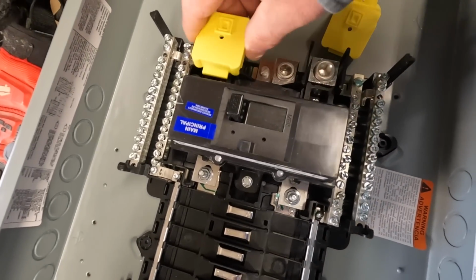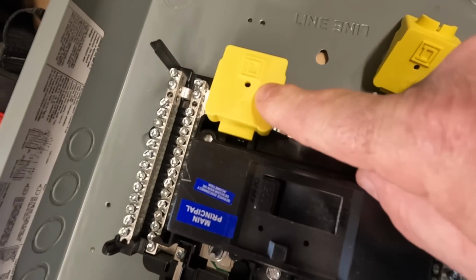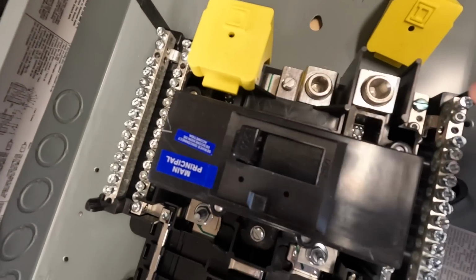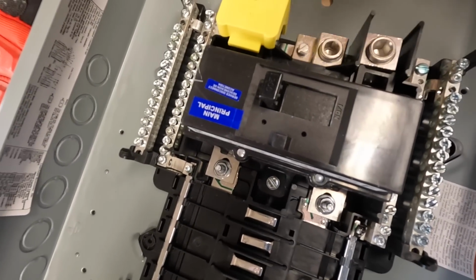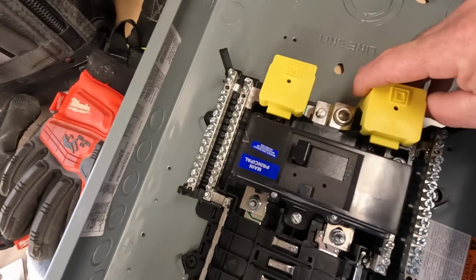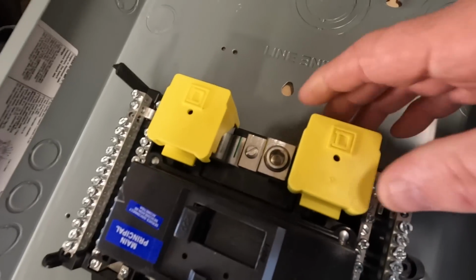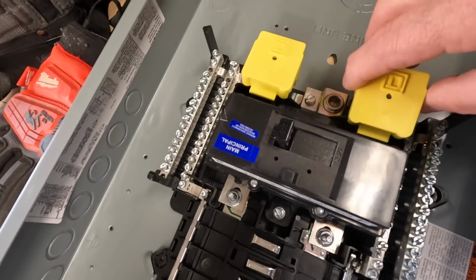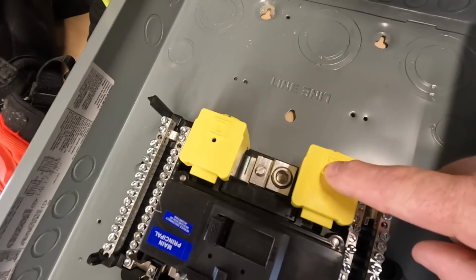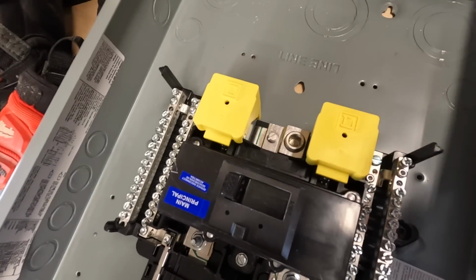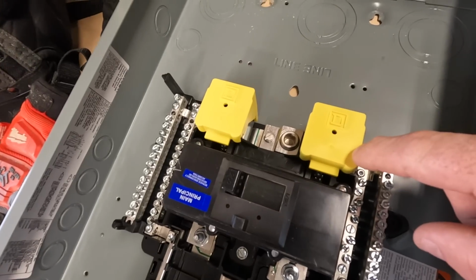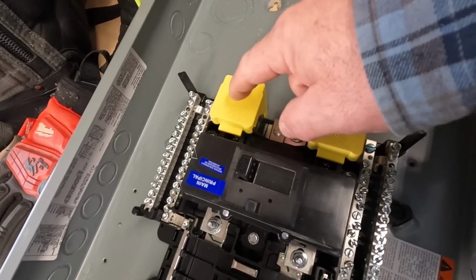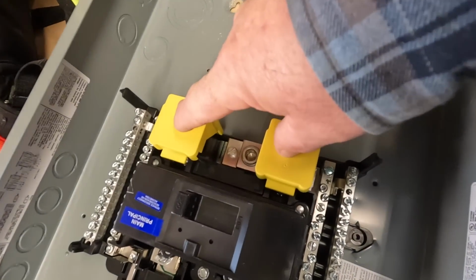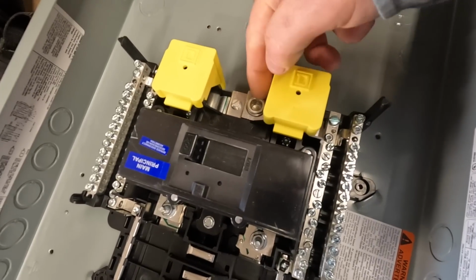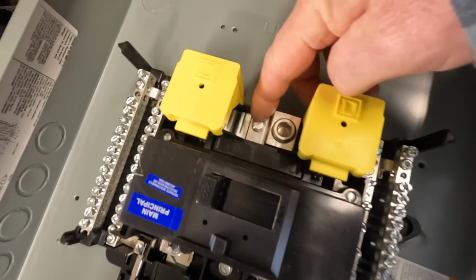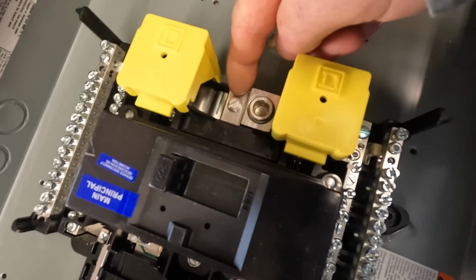The thing I like about the Square D is they leave this little probing hole right here so you can put your testers in there to check for proper voltage. I know sometimes I forget to put these on before I energize the service. I usually don't need to use these holes, but the idea is to put these on before you energize the panel, so you're not subject to getting shocked by these two terminals. These are the main service entrance conductors right here. Here's our neutral, and of course the grounding electrode can be connected here on this particular terminal.